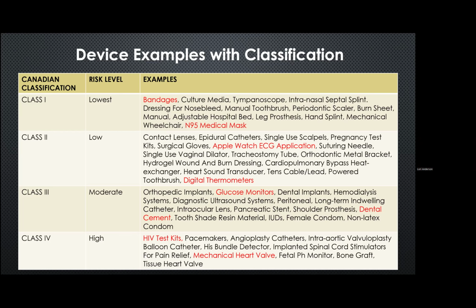The next class we look at is Class 2. That's our second lowest class device. So here I've got some examples: surgical gloves, TENS machines. We see a lot of electric stimulator devices that fall into this category. A fun one to consider is that the Apple Watch ECG app is a medical device. So the watch itself is not, but the app on that device is a Class 2 medical device. Digital thermometers were really important to consider during the pandemic, making sure that when people were acquiring digital thermometers for use, they were licensed.